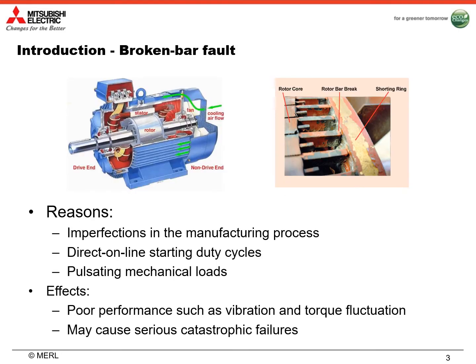Broken rotor bar fault is one of the major faults in squirrel cage induction machines. It can be caused by imperfections in the manufacturing process, direct online starting duty cycles, or pulsating mechanical loads. Once the bar is broken in a squirrel cage induction machine, it can cause poor performance such as vibration and torque fluctuation. Even worse, it may cause serious catastrophic failures.